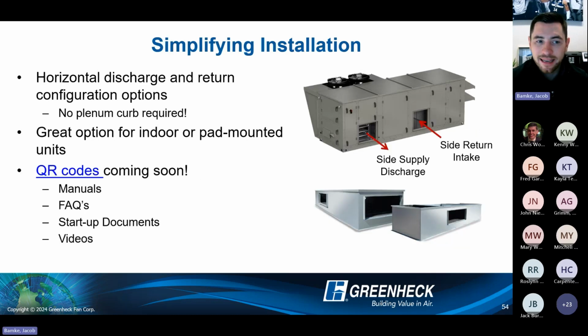So, simplifying installation. One thing we like to make sure of is that we have high quality components that work well, but we also want this to be easy to install. A couple of ways that we do that. One is horizontal discharge and return configuration options. This removes the need for the plenum curb. So whether you have side supply and return, you might have some end return options. This gives you the benefit to pad mount it or keep a low profile design and eliminate the need for a plenum curb with a potential service platform, but still get the benefits of the horizontal connections.